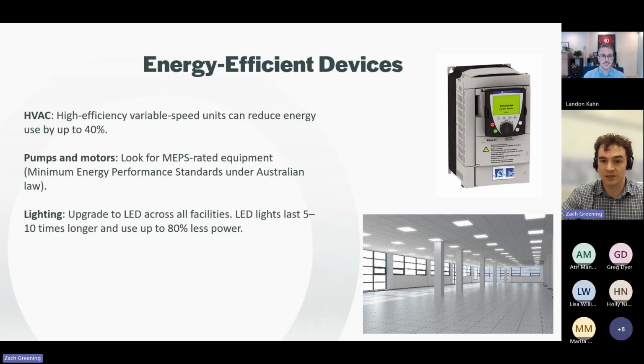So when you're looking at some of these upgrades, check out your chilled and hot water pumps, cooling tower fans, supply and return air fans, and your kitchen exhaust and car park ventilation motors. So these kind of unglamorous, often forgotten about areas tend to have the most inefficient equipment in there, so they're always worth a look if you're considering an upgrade.